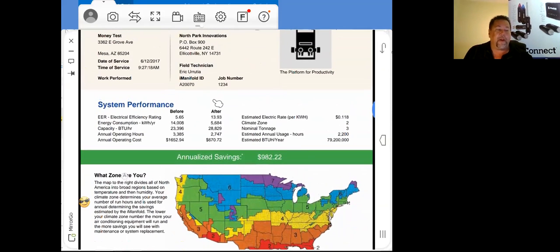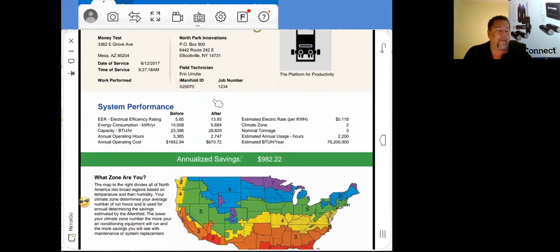Now, when we took the snapshot in, we've got an EER right here of 5.65. We did some adjustments, did some modifications and everything, got this thing working perfectly, and now we've got a 13.93 EER after that. So calculating this, before we were running at $1,653 basically per year to run the system. After we did this adjustment, we're down to $670.72. So we just saved this customer $982.22 annually just from this fix.